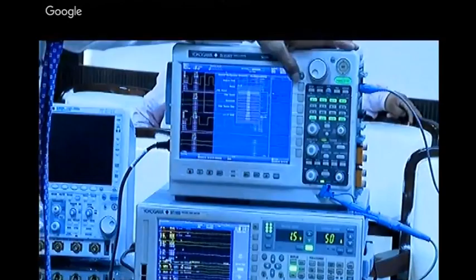Then analysis function, power analysis also. You can change the wiring diagram: 1P 2W or 3-phase 3-wire, 3-phase 4-wire, 3V3A method. You can configure and set which channel is voltage and which is current. You can do harmonic analysis, set it for line or power, choose which channel, and then see the harmonics also.